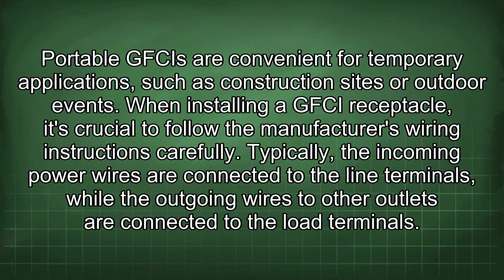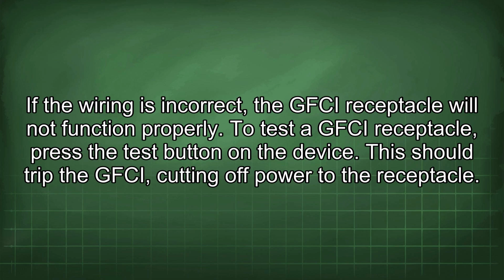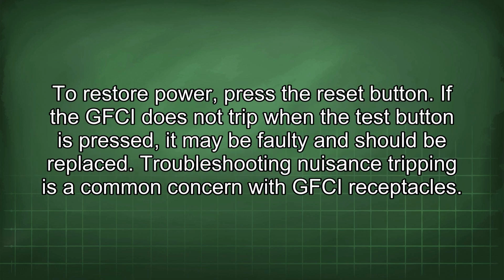When installing a GFCI receptacle, it's crucial to follow the manufacturer's wiring instructions carefully. Typically, the incoming power wires are connected to the line terminals, while the outgoing wires to other outlets are connected to the load terminals. If the wiring is incorrect, the GFCI receptacle will not function properly. To test a GFCI receptacle, press the test button on the device. This should trip the GFCI, cutting off power to the receptacle. To restore power, press the reset button. If the GFCI does not trip when the test button is pressed, it may be faulty and should be replaced.